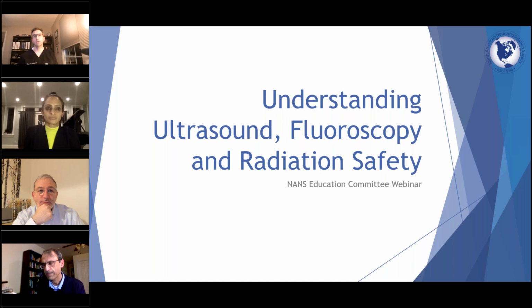Yeah, anything that you have under the X-ray machine that the X-ray machine views as obstructing the beams reaching the intensifier, then the automatic brightness control will pump out more radiation. That's no doubt. So if you have lead-lined gloves and the machine sees the lead-lined gloves, it thinks it needs to put out more radiation. So a pointer, all those things will increase your exposure, because the automatic brightness control is going to adjust based on the fact that it thinks there's something obstructing the view of radiation and impeding the radiation from hitting the image intensifier.